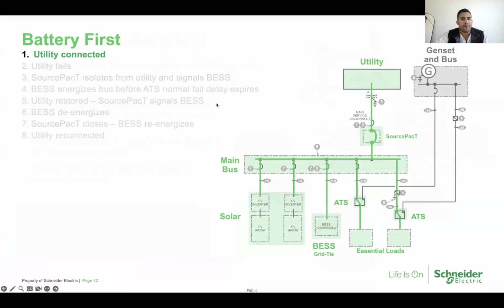We'll go through an animation here on a design that we've worked with that's similar to this approach. In this design, we have an incoming utility. We have the main service disconnect. Downstream of the main service disconnect is our SourcePacT automatic interconnection device feeding a main bus. If you look at that AC system, on that main bus we have 2 PV arrays connected. So during grid tied operation, the PV systems are in parallel, grid interactive, providing power to the system. We have our energy storage system as well. It's connected to this main bus, and we have 2 breakers for ATSs that are providing power to essential loads.